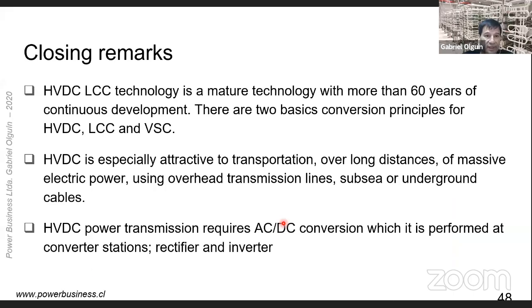So, closing remarks. HVDC technology is a mature technology with more than 60 years of continuous development. There are 2 basic conversion principles for HVDC today, LCC and VSC. HVDC is especially attractive for transportation of massive electric power over long distances using overhead transmission lines, subsea or underground cable. HVDC power transmission requires AC-DC conversion, which is performed at the converter station, operating as rectifier and inverter.